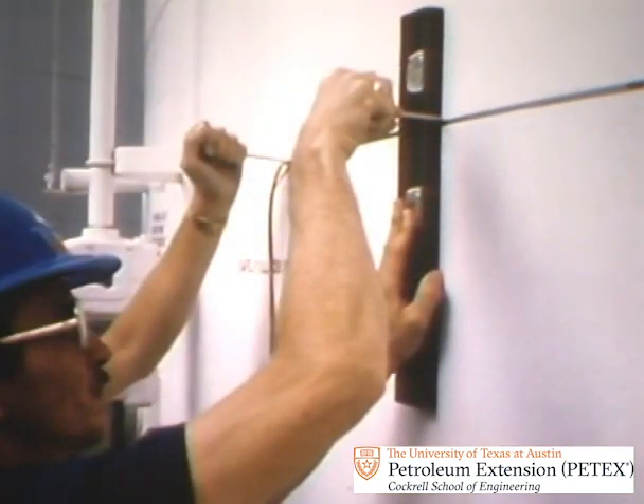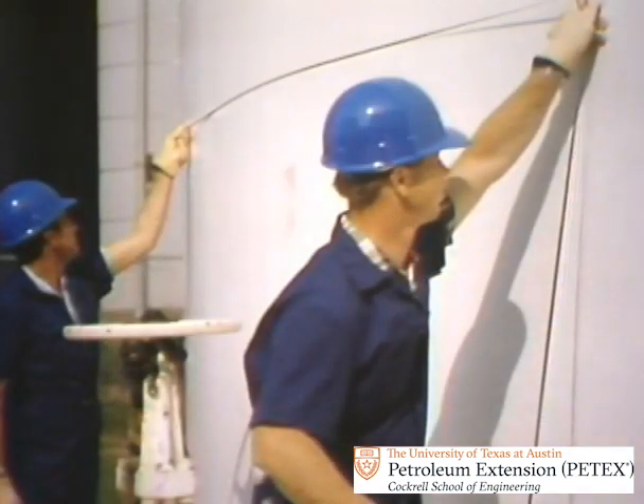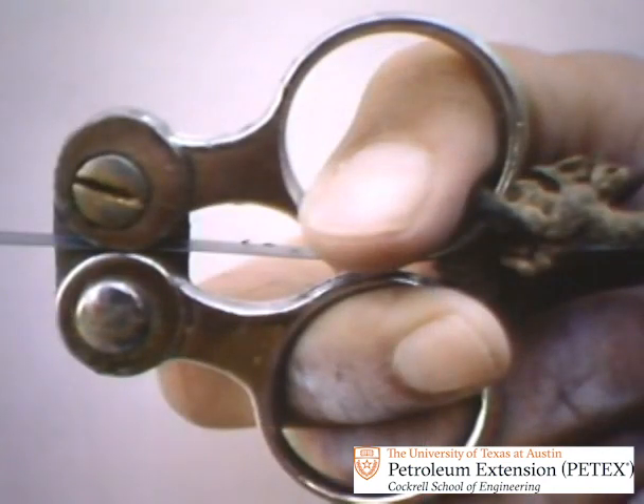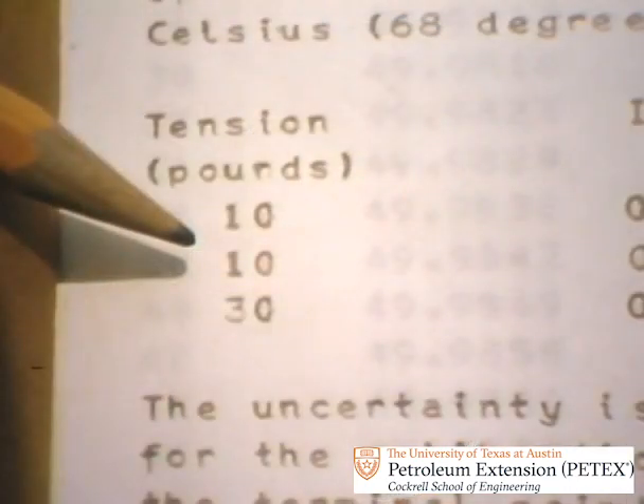While one crewman anchors the standard tape on the indentation, another makes a vertical score at the zero reading. This marks a zero reading on the tank. Then they extend the tape on the ring. They make certain that the tape stays precisely on the path marks. Using a tape clamp, the crewman gently pulls on the tape to get the required tension on it. Required tension is read from the NBS calibration report that comes with the standard tape. In this case, it's 10 pounds.